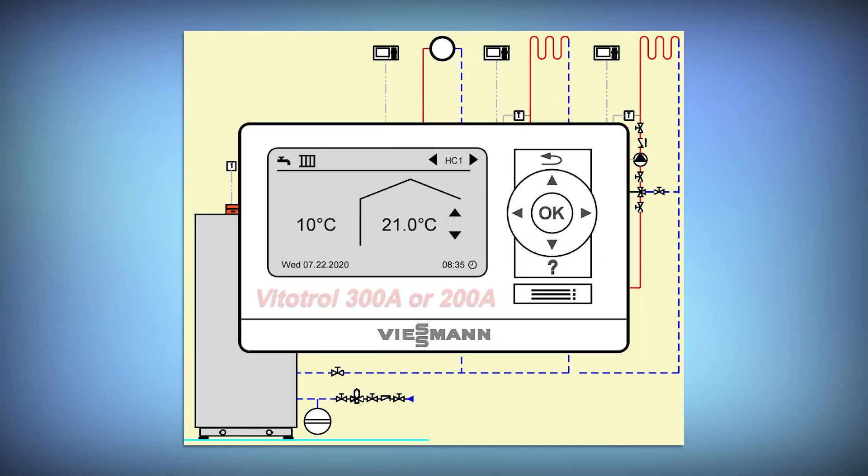The Vitotrol 300A or 200A are room sensing devices that communicate with the boiler in real time and as the room approaches set point they don't turn the boiler on and off but tell the boiler to make adjustments to the way it operates.